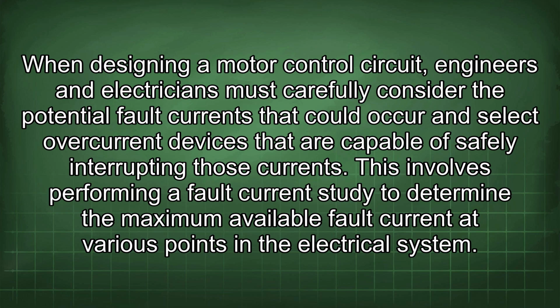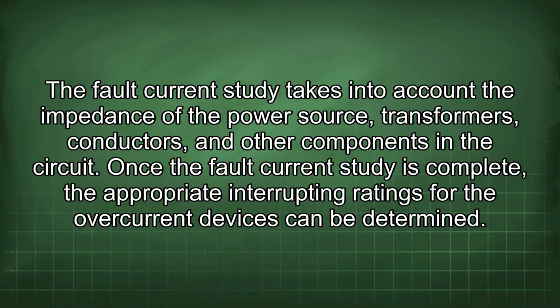When designing a motor control circuit, engineers and electricians must carefully consider the potential fault currents that could occur and select overcurrent devices that are capable of safely interrupting those currents. This involves performing a fault current study to determine the maximum available fault current at various points in the electrical system. The fault current study takes into account the impedance of the power source, transformers, conductors, and other components in the circuit. Once the fault current study is complete, the appropriate interrupting ratings for the overcurrent devices can be determined.